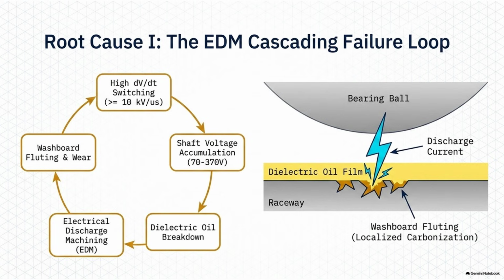Fluting, okay. So you have taken a perfectly engineered frictionless steel bearing and turned the inside of it into a burnt, pitted washboard. Which means it's not going to spin smoothly anymore, right? Not at all. And that leads us to the second phase of this failure chain. The sources call this dynamic eccentricity and spatial harmonics. But physically, it's just a wobble, right? It is a wobble, yeah. But the scale of the wobble is what makes it so fascinating here. How small are we talking? Well, as the bearing wears down and that washboard pattern deepens, the rotor it supports is no longer spinning perfectly true. It starts to vibrate off its center axis. The engineering document specifies a total indicator reading, a TIR, of greater than 0.05 millimeter. 0.05 millimeters. Wait, that is roughly the thickness of a human hair.